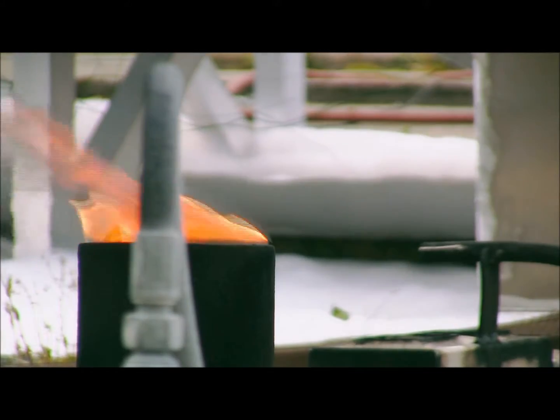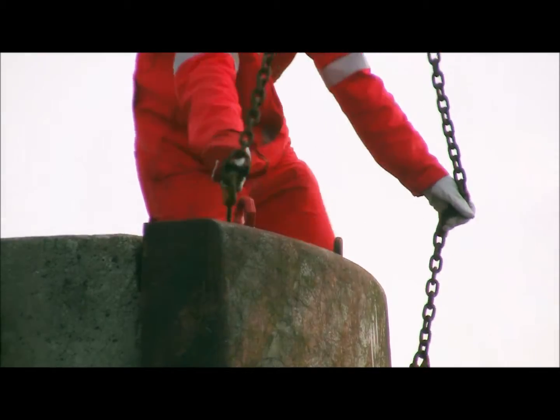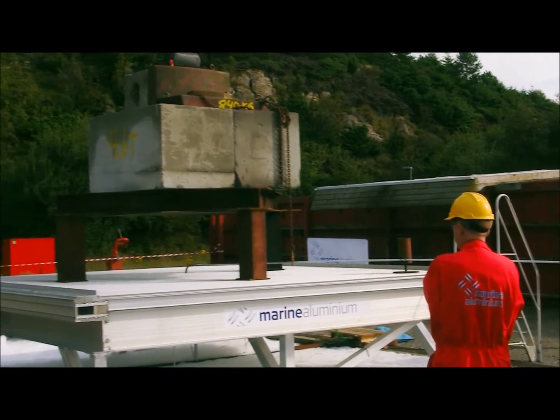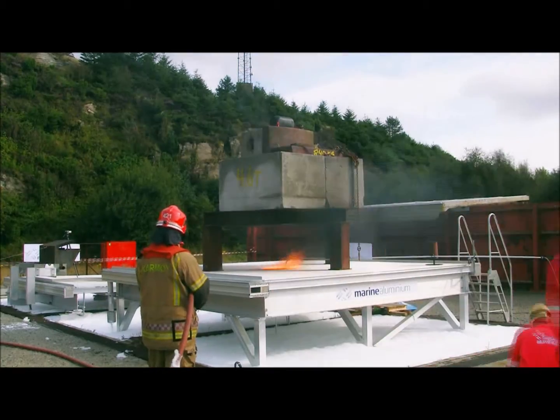The purpose of the fire resistance test is to prove that the SafeDeck in aluminium is equal to steel with regard to resistance from pool fires on top of the deck. The test is performed with a load simulating an S92 helicopter on top. A fire source simulates a continuous leakage from a helicopter fuel tank over a duration of 10 minutes.